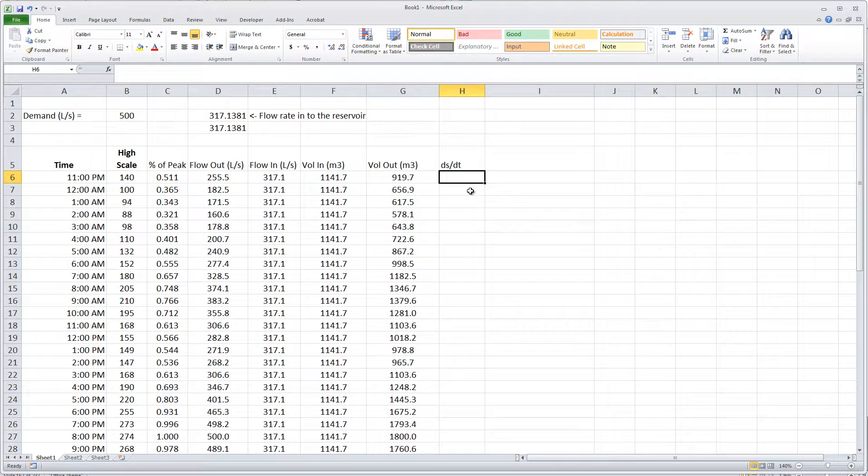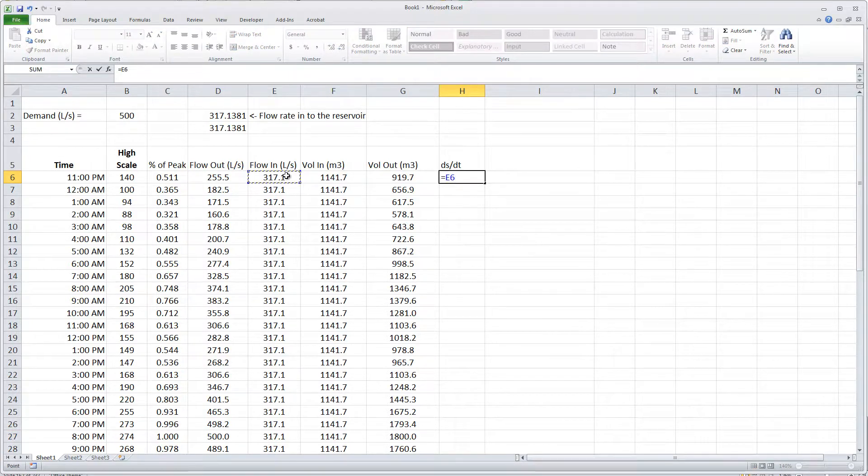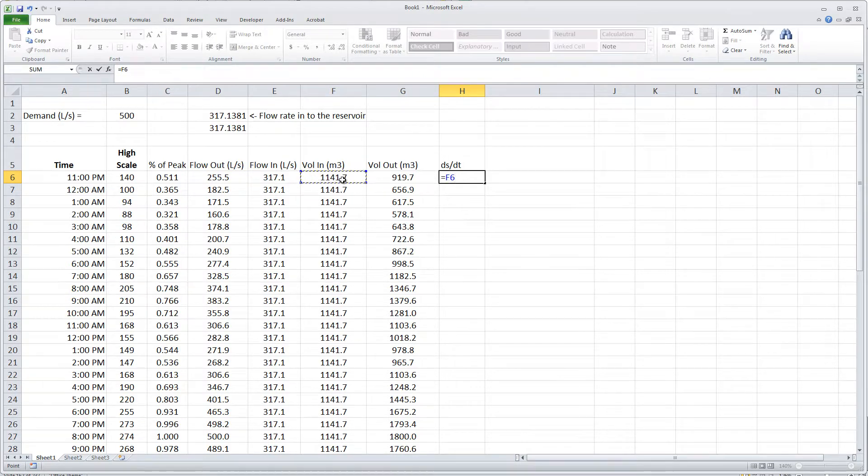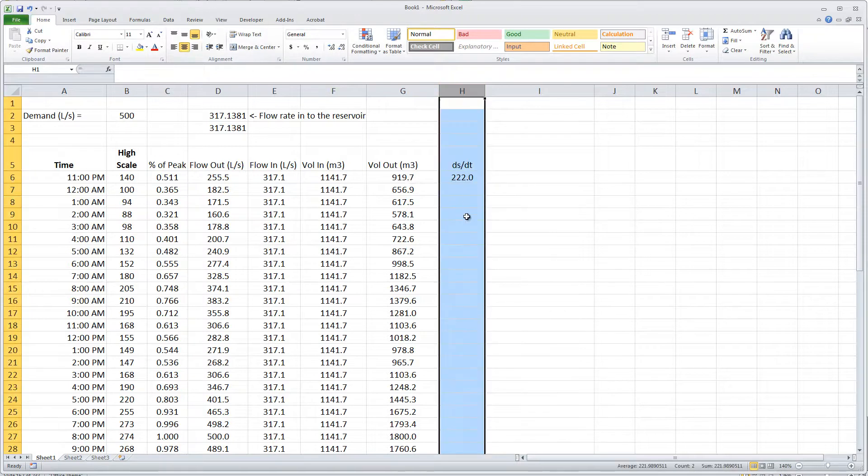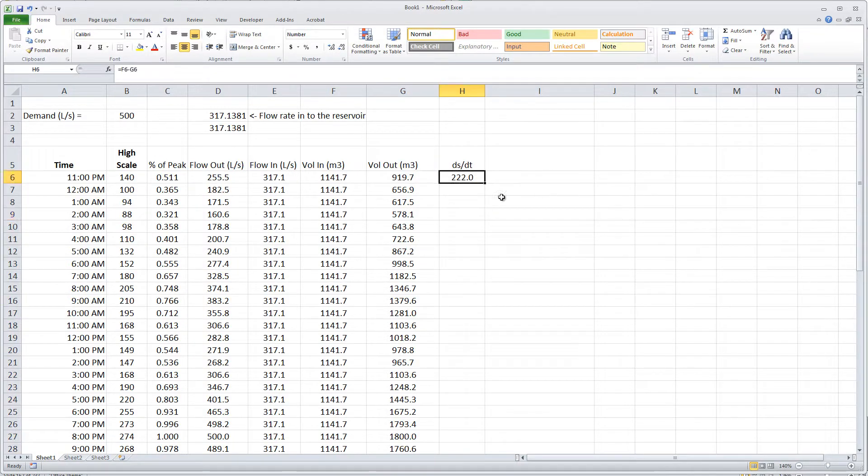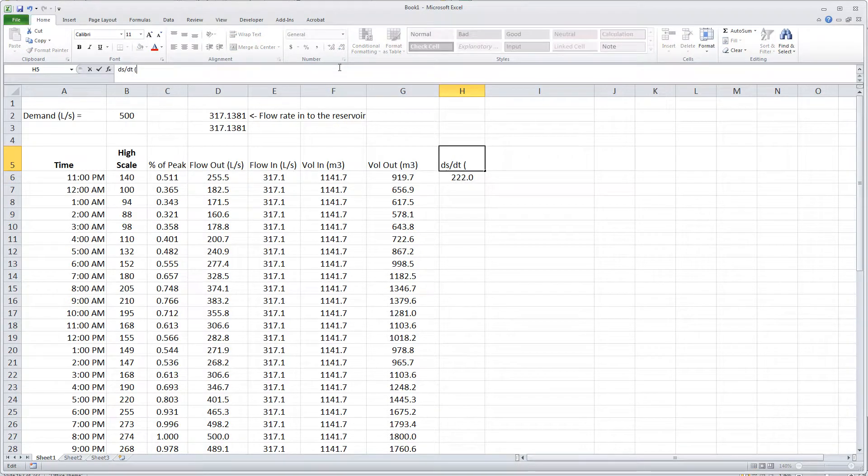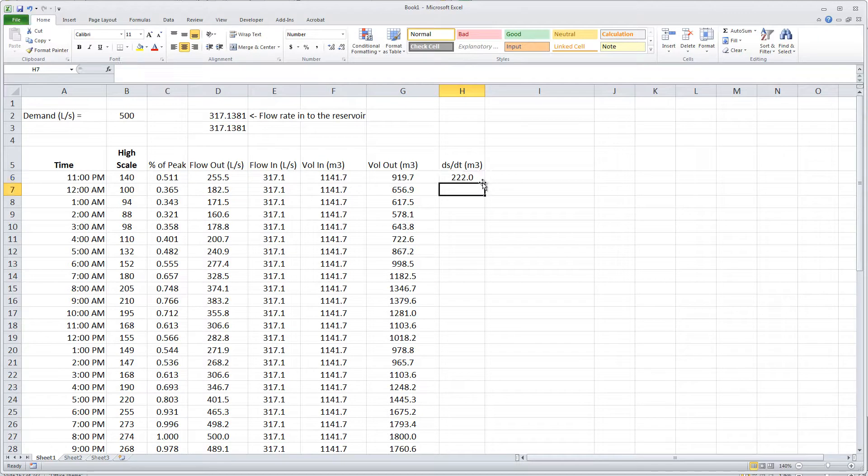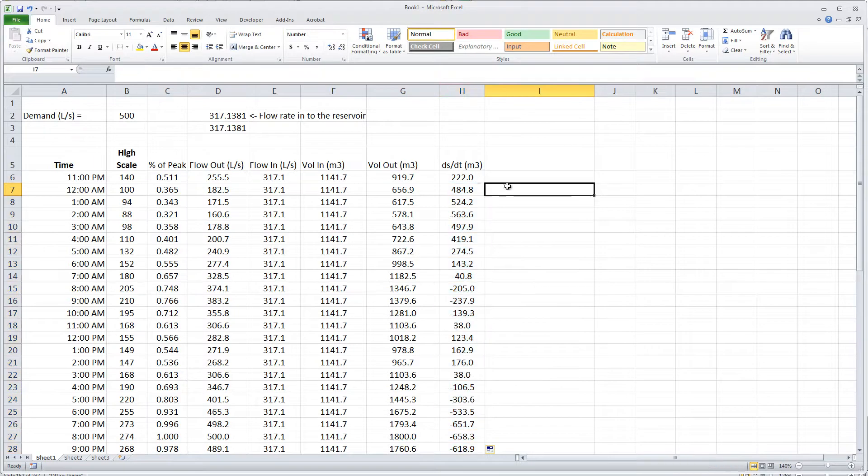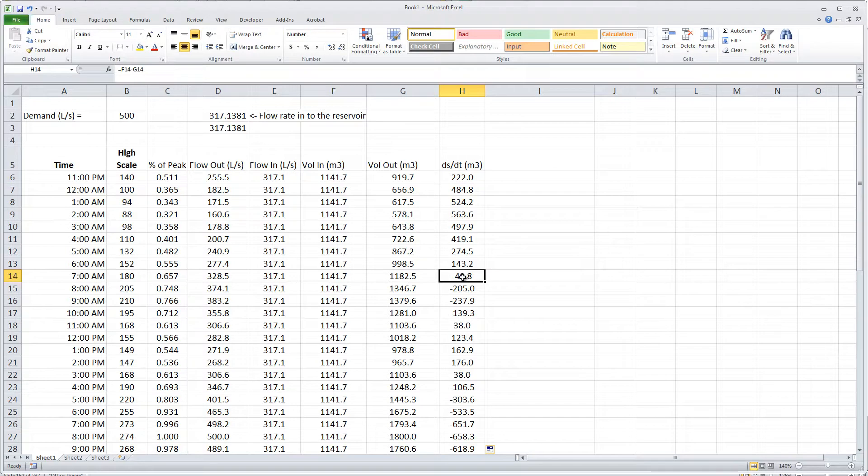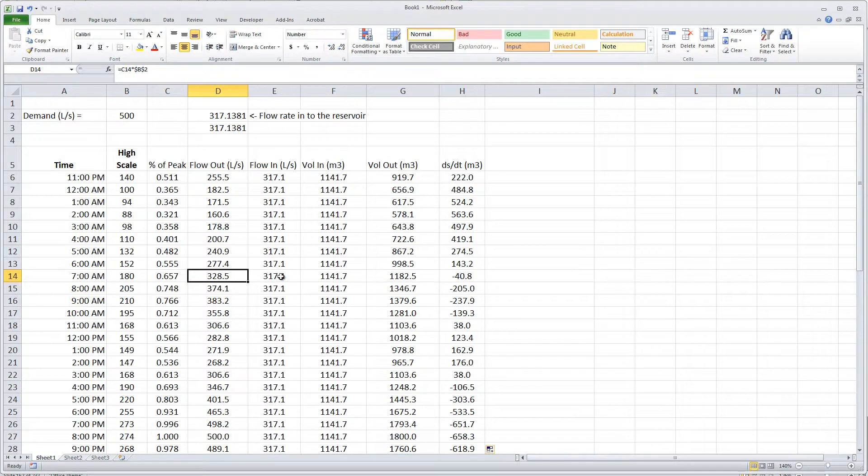DSDT is simply the difference between the in and out, so the volume in minus the volume out. We can see that in this first hour, during the 11 o'clock hour, there's 222 liters, I'm sorry, this is cubic meters. Now I can double click that to get it to go through. Certain periods of the day the reservoir is filling when it's positive, and when it's negative that means that the reservoir is emptying because when it's negative the flow rate out is bigger than the flow rate in.